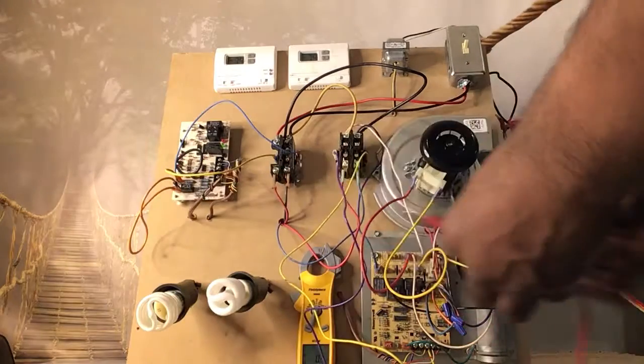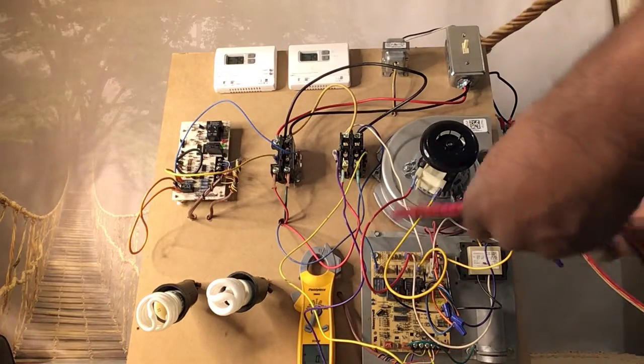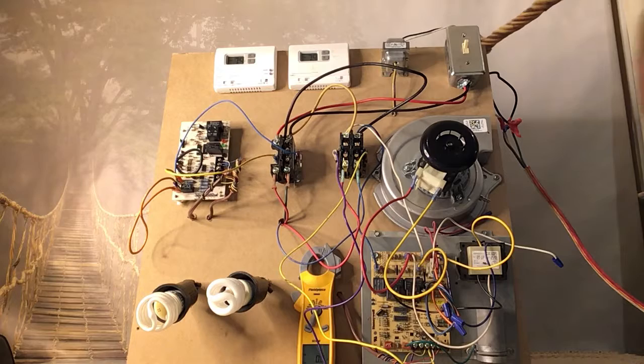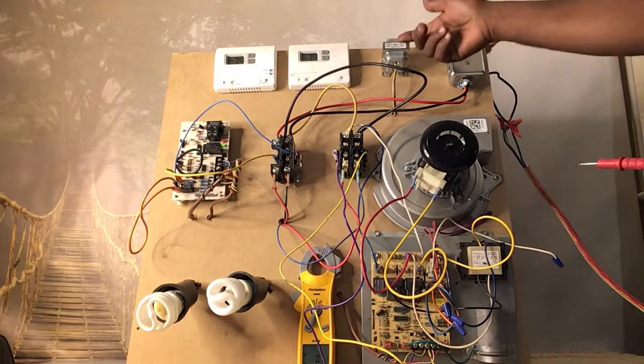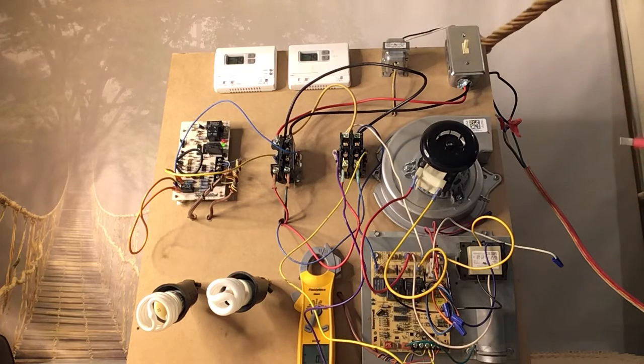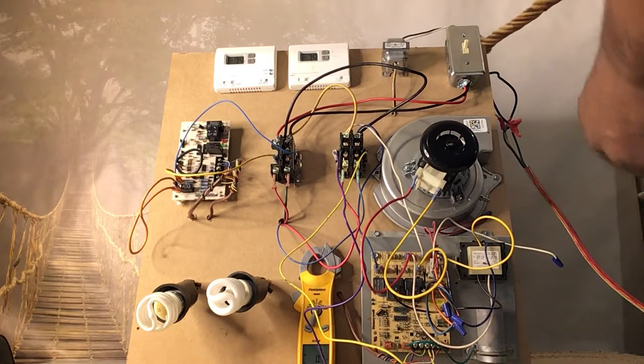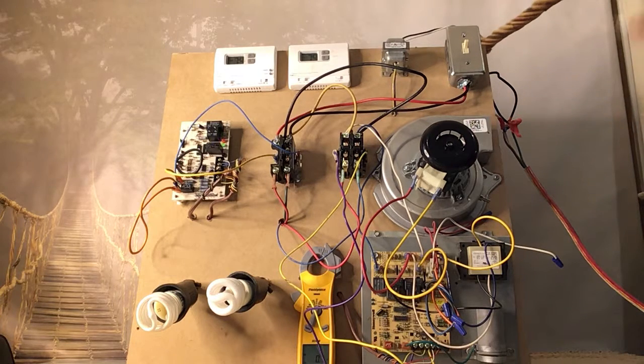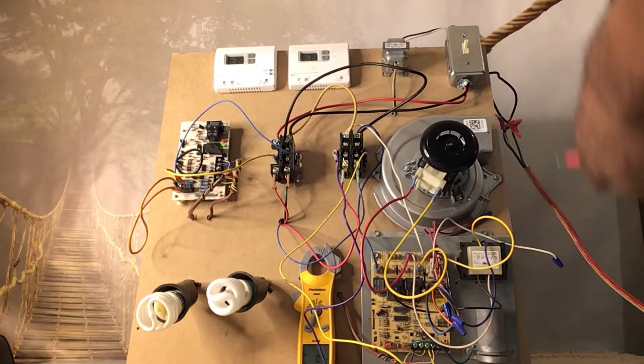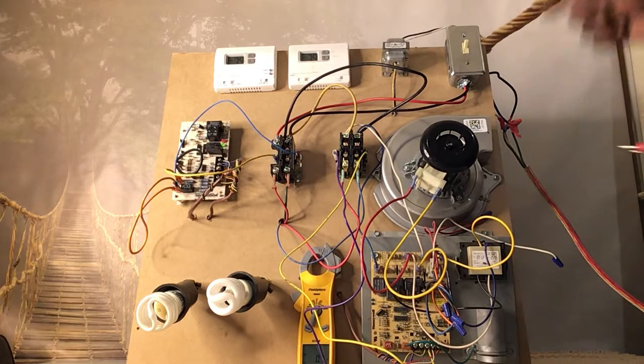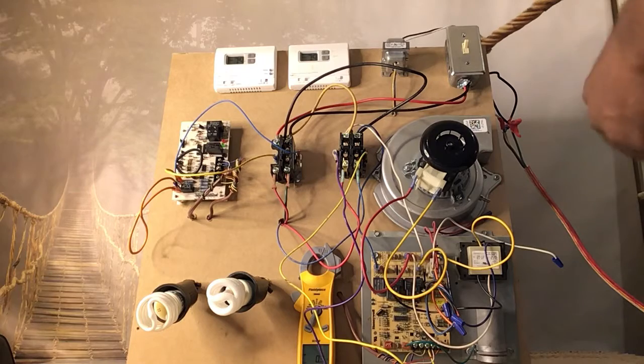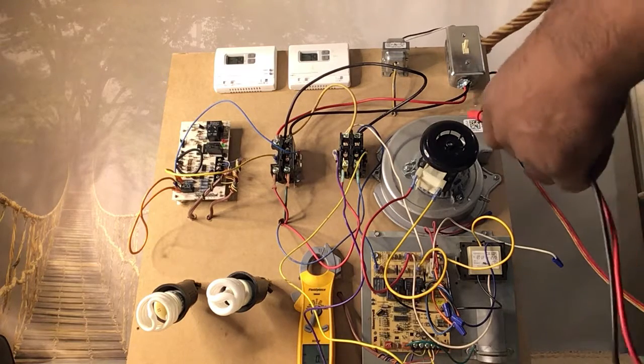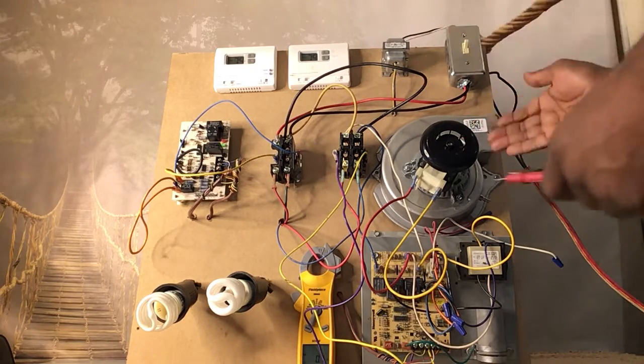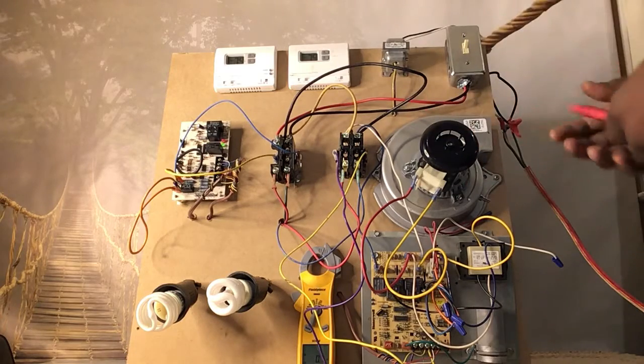All right, let's run through it real quick one more time so that we're all on the same page. This right here is my switch where my high voltage lays. This is my transformer, actually referred to as a step down transformer. Super important. And these are all steps. Whenever you're troubleshooting and your unit is not working, these are the steps you want to follow. You want to make sure that you have power. Once you verify power, you want to make sure that you have 24 volts, because without 24 volts you cannot run anything on the system. Everything is controlled by 24 volts.